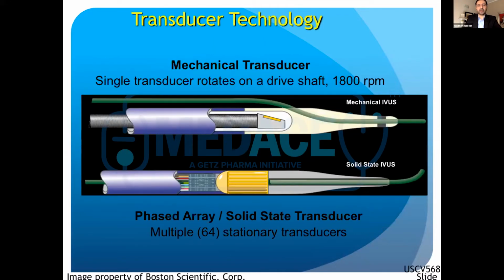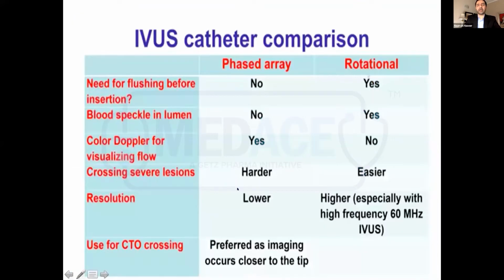There are two types of transducer available. There's a mechanical transducer, which rotates on a drive shaft at 1800 RPM, which is the Boston Scientific technology. And there's the Volcano, now taken up by Philips, solid state IVUS technology, which has 64 stationary transducers that emit ultrasound waves. Both have their nuances.